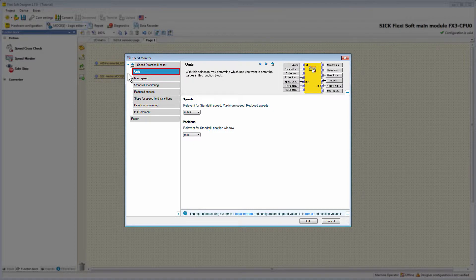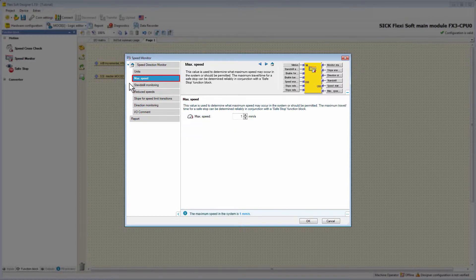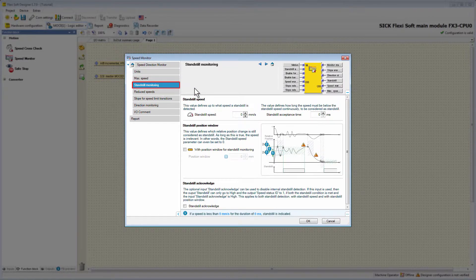We take a look at the speed limits configuration, jumping to the next tab, Max Speed, where you can determine what maximum speed may occur or should be permitted in your system. The opposite of Max Speed is found on the tab Standstill Monitoring, where we can set the Standstill Speed — defining up to what speed a standstill is detected — and a Standstill Acceptance Time. This time defines how long the speed must be continuously below the standstill speed to be considered as standstill, preventing a standstill detection if the drive only changed its movement direction.